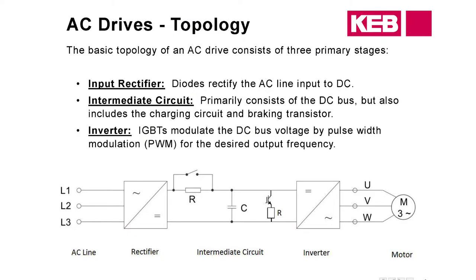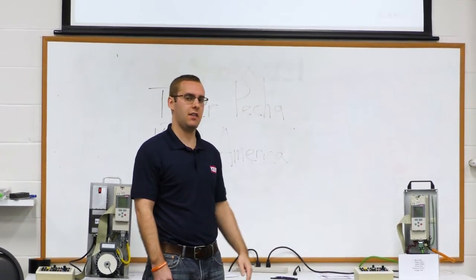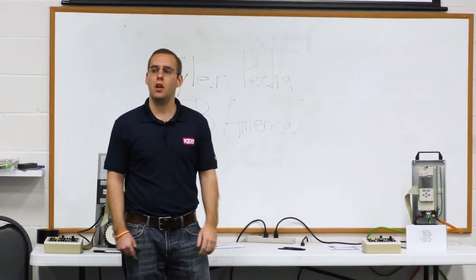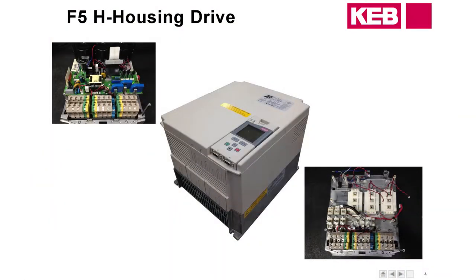Every drive is going to have three main parts. You're going to have your input rectifier, which takes your AC voltage and turns it into DC voltage. You'll have your intermediate circuit, which contains a DC bus, a braking transistor, and a charging circuit. Then you have the actual inverter output containing the IGBTs, which take that DC bus voltage, pulse on and off very quickly, and simulate an AC sine wave out to the motor. Throughout the presentation we'll feature our H housing drive. The internal workings are very similar across housing sizes — what you have in front of you is a G housing, so everything will look very similar but laid out a little differently internally.